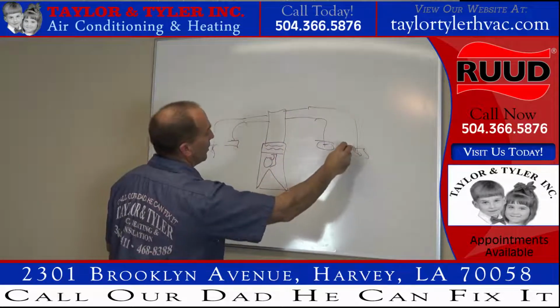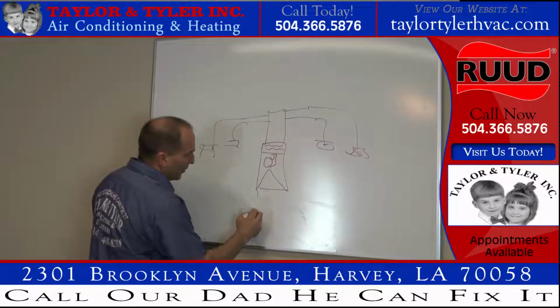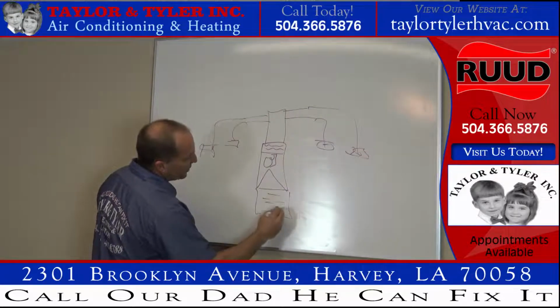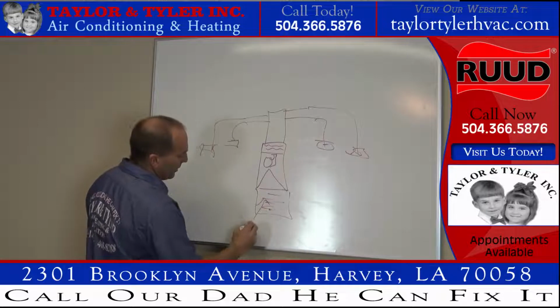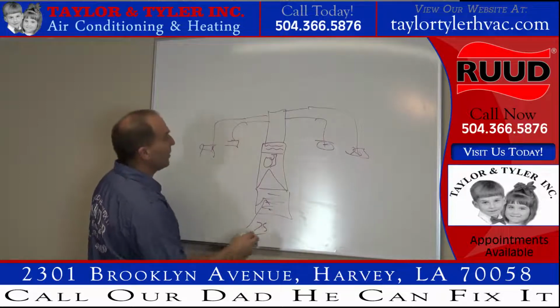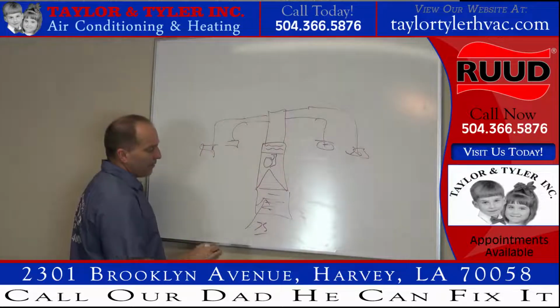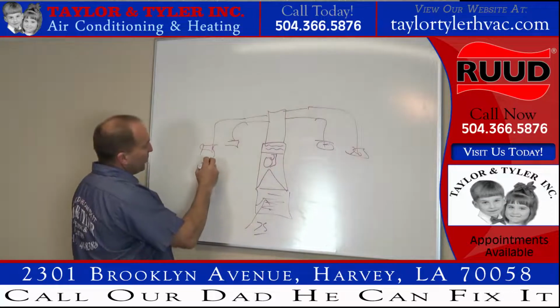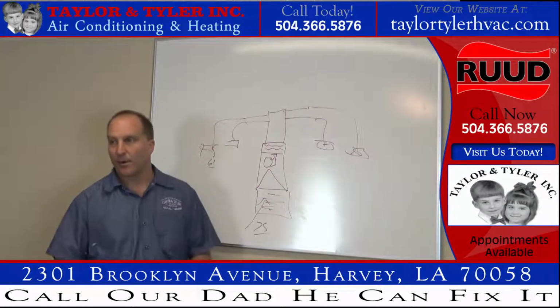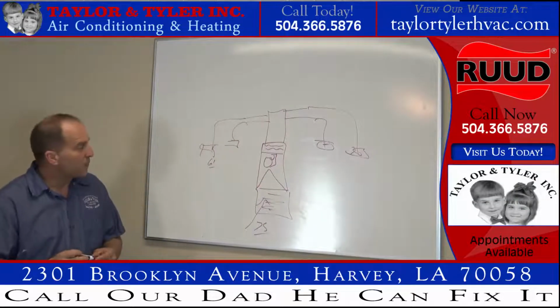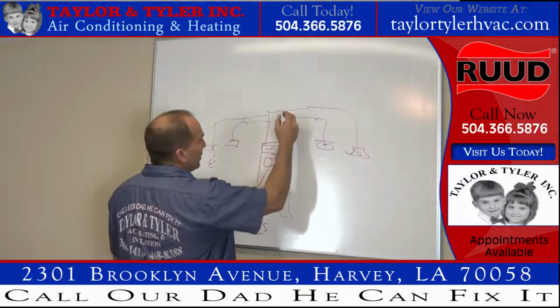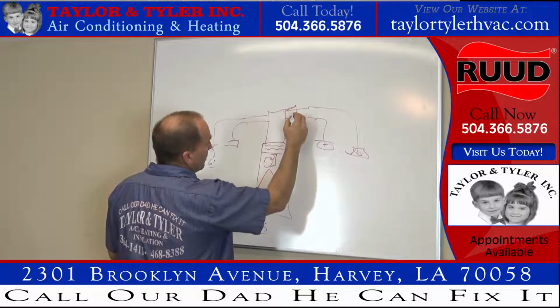I got 4 ducts all the way in my house, right? Got a return air below here, I got a return grill sitting here, airflow's going in here, it's 75 degrees going in here, coming out of here, 14 degrees is going to give me 61 degrees coming out of my supply, right? Okay.